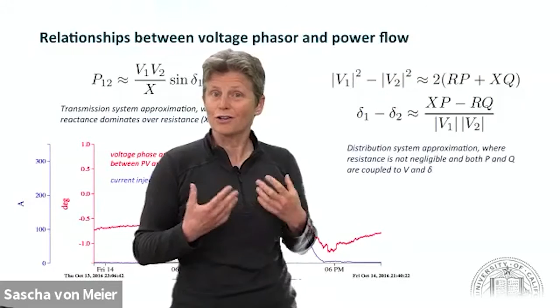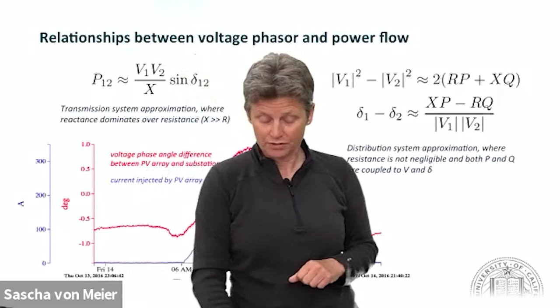So what happens when you have appreciable resistance, these quantities get intermingled, and the phase angle difference, where we're making a small angle approximation, is no longer just related to real power flow, but also to reactive power flow and resistance. So it gets more complicated, and this is kind of a foreshadowing that the ratio of R and X is an important determinant of how a control system is going to work, because again, these variables are coupled together. But it's common at the transmission level for operators to think about phase angle differences as being indicative of real power flows.